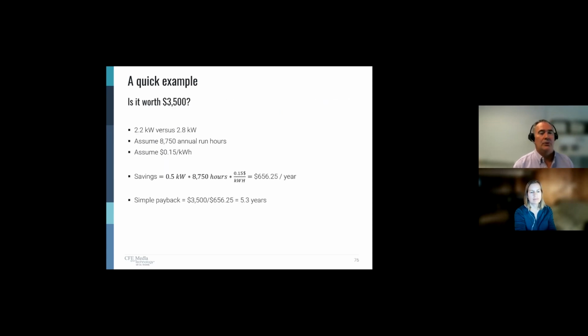So the question is, is it worth the $3,500 to put the synchronous motor in place? I'm not going to do the $1,100 calculation because you'll get the idea. So it's 2.2 kW versus 2.8. We're going to assume 8,750 annual run hours. Your mileage may vary. And I'm going to assume you live somewhere like in Texas where electricity is relatively cheap and it's only 15 cents a kilowatt hour and there's no demand penalty. So you go through the math and you're going to save about $650 a year. So a simple payback says in 5 years, that motor is going to pay for itself.